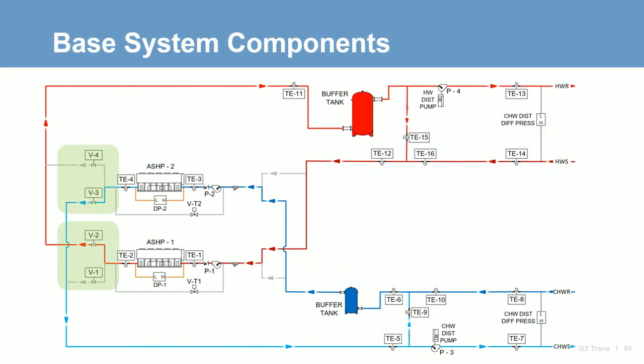Speaking of changing modes, let's look at the parts and pieces that make this work. The first parts are the isolation valves at the exiting, cooling, and heating lines of each unit. These valves could be tied to the unit controllers to stroke open or closed based on the unit mode of operation. The coordination of these valves with the unit mode of operation is imperative to system operation to ensure that the unit is providing the correct condition fluid to the correct loop.